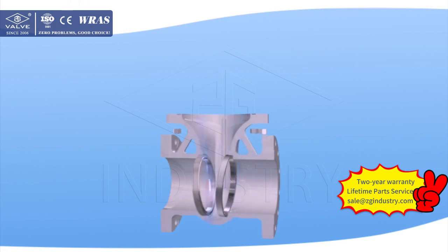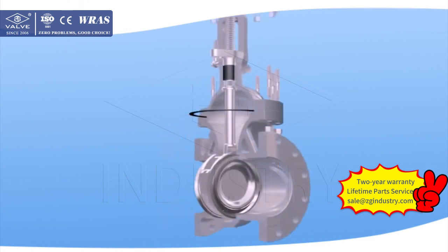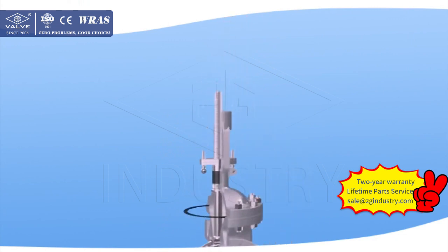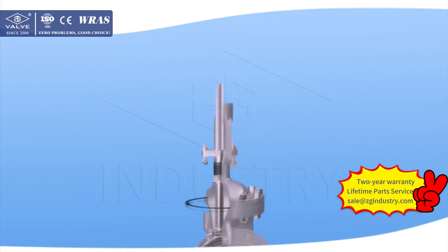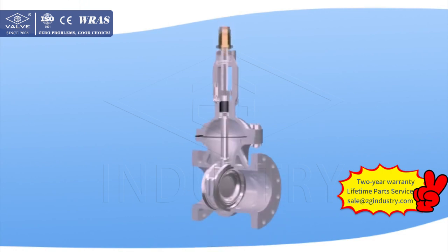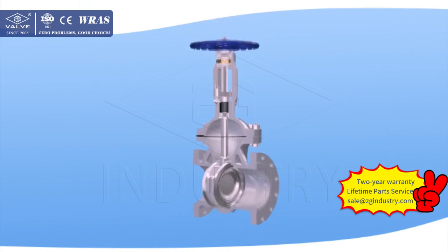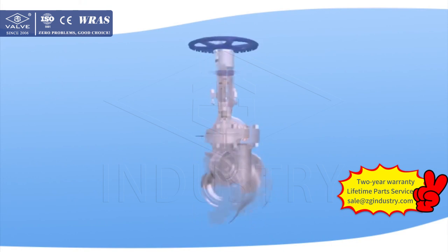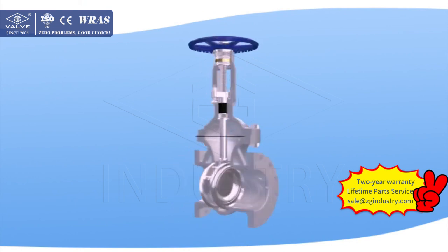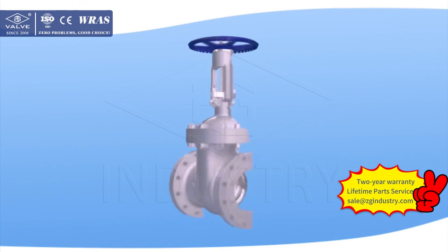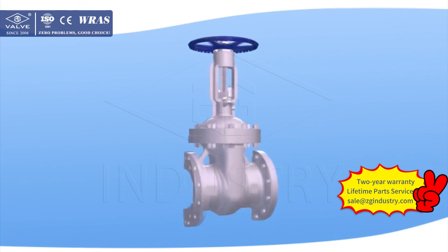Wedge gate valve has the following advantages. 1. Small flow resistance. The sealing face suffers less flush and corrosion. 2. Low torque operation. Easy operation. 3. Direction of medium is not limited, does not generate disturbed flow and does not reduce medium pressure. 4. Simple structure. Short face-to-face dimension. Processed precisely and widely applicable.